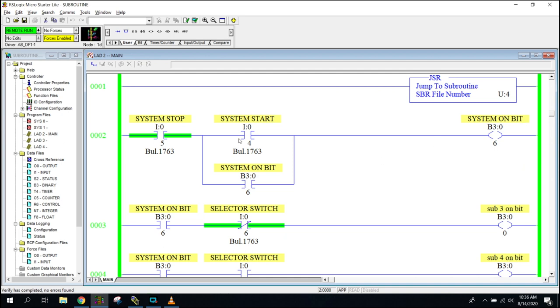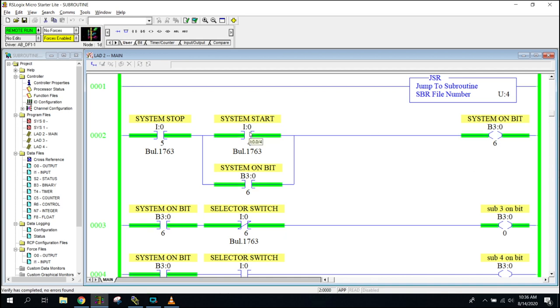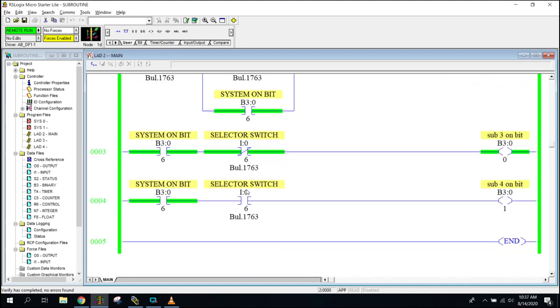So what we're going to do is, this is just a typical motor control style latching circuit. When I go ahead and press my green system start button, it's going to latch that B3 on over here - it's going to latch itself on right here.